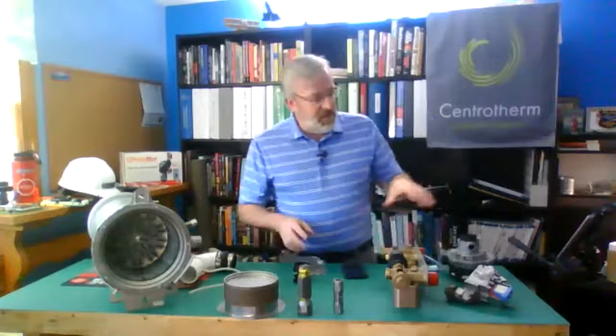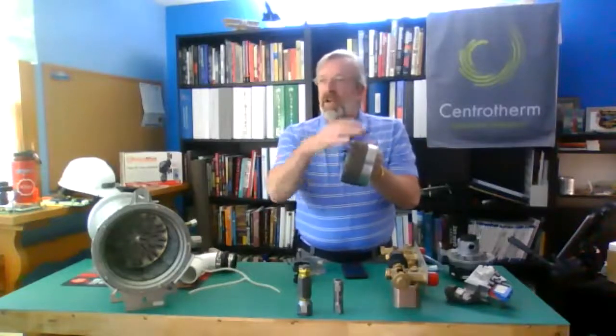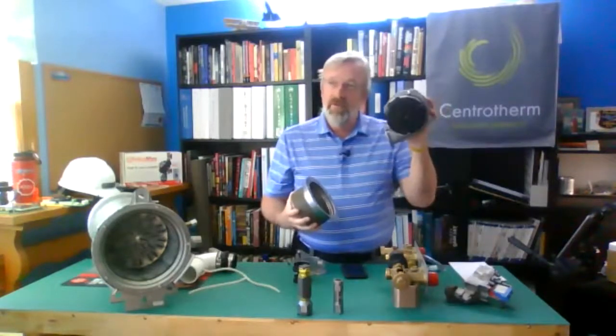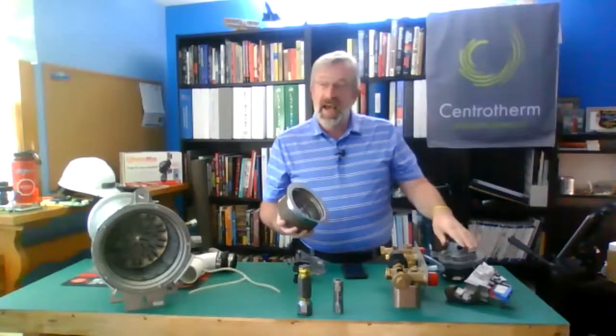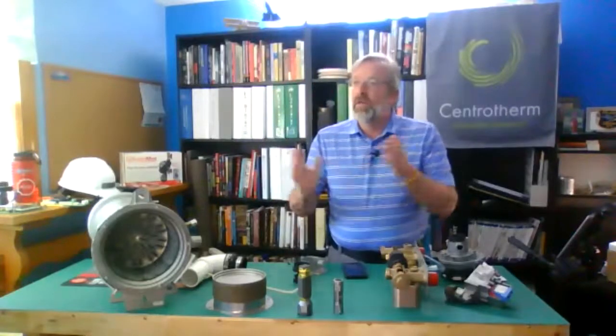So where does that all fit together? If we've got fuel, we've got spark, we really want to look at our air to gas ratio. We want to look at our air. So if I'm pulling air through here and I'm pushing it out here, if I have a dirty burner, lack of service, something like that, that's going to restrict the air moving through my fan. It's going to change the negative pressure I'm applying to my gas valve. We're going to get some adjustment, but there may get to a point where we can't be adjusting anymore, and my air gas mixture gets out of whack. And now we've got to look at getting that back into where it needs to be.